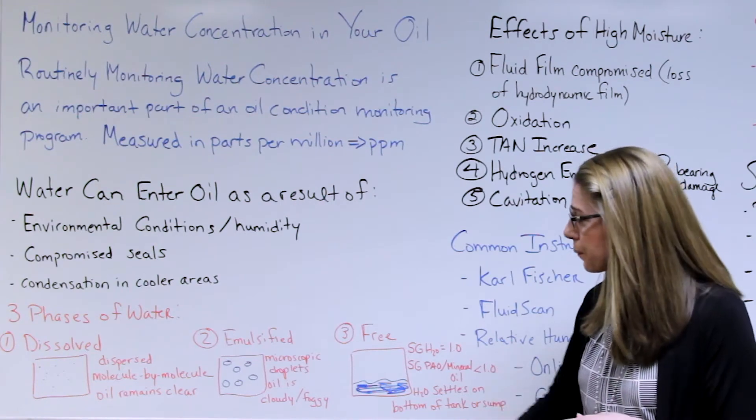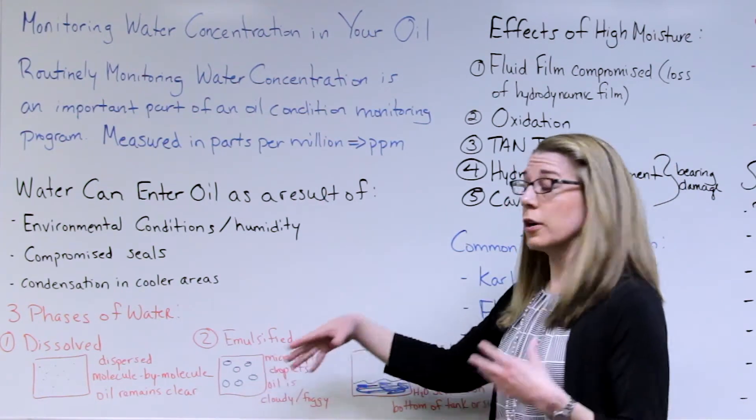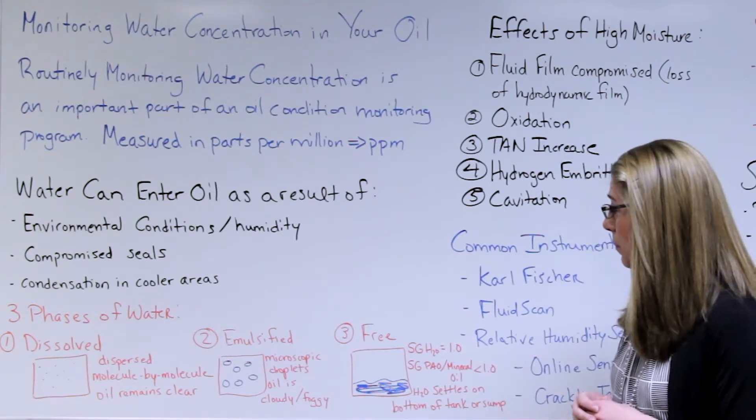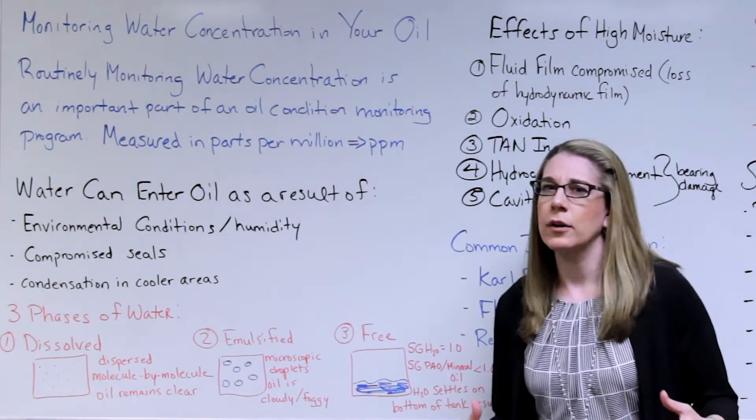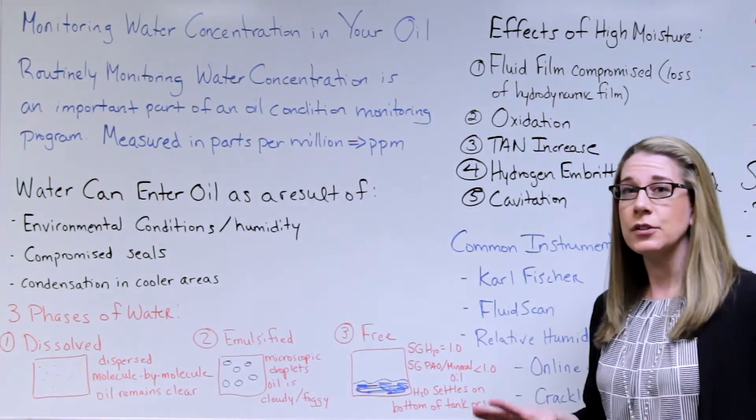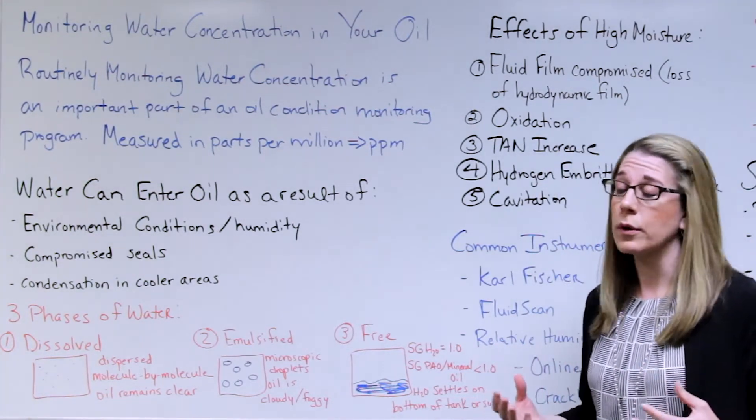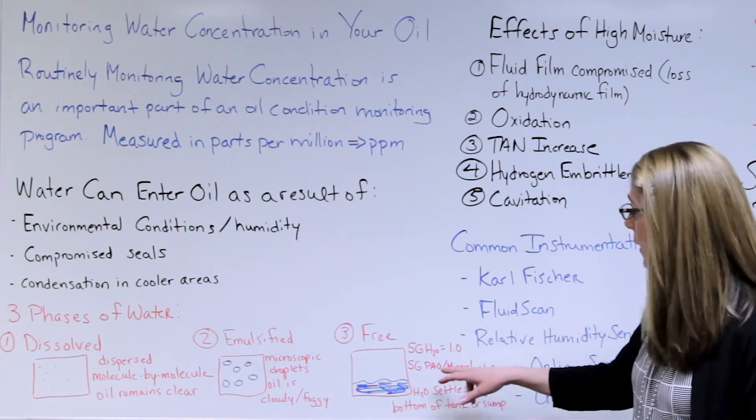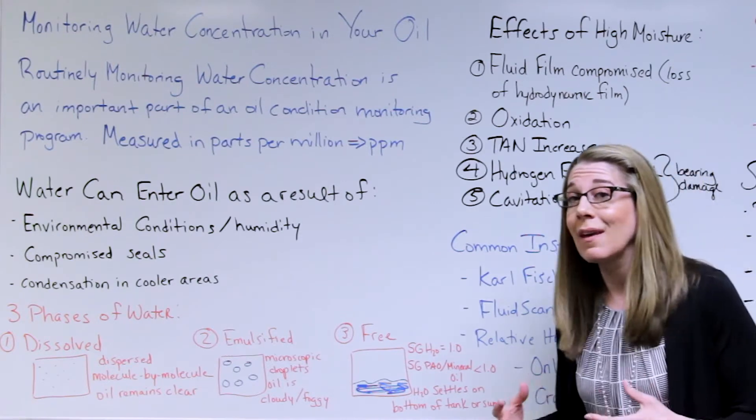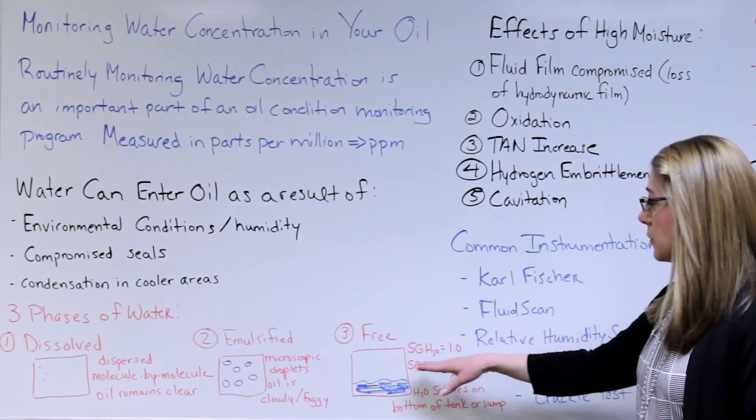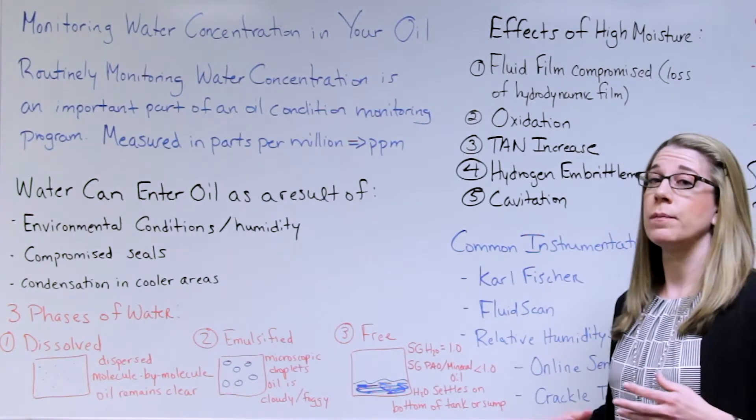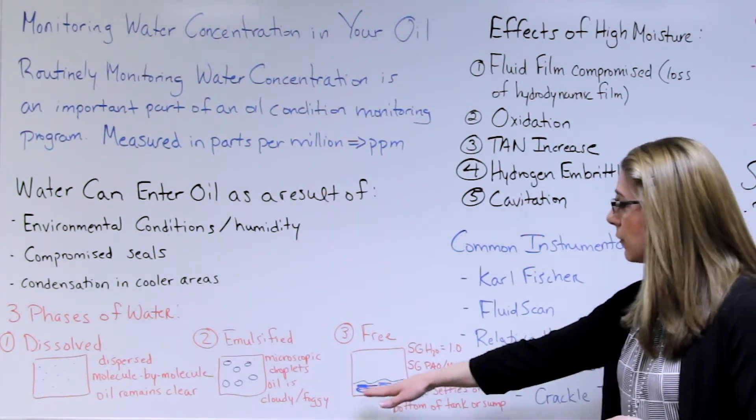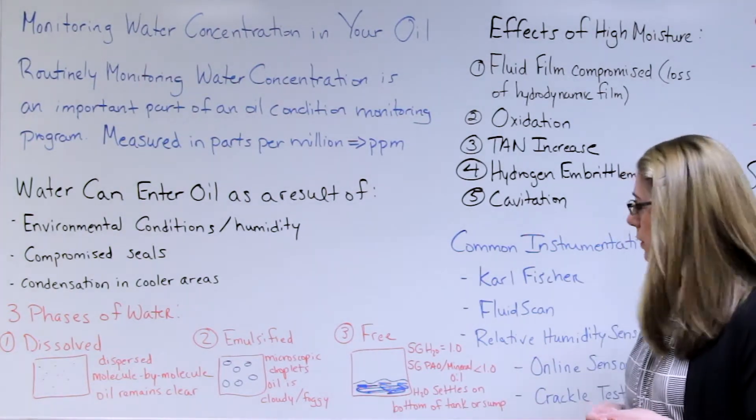Once we hit that point where it's no longer an emulsion, we start getting free water that's sitting in the bottom of the sump or tank. Why does water sit at the bottom of the tank? It has to do with specific gravity of the water versus the oil. Typically in PAOs, so PAO synthetics and mineral oils, we have a specific gravity that's less than one, and the specific gravity of water is one. That water is going to sink to the bottom of the sump or tank. If you've ever seen that, that's the point where you have free water in your system.